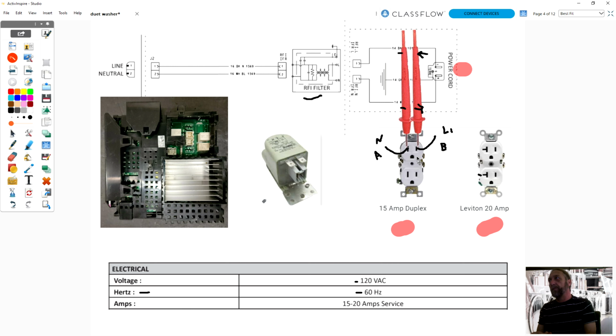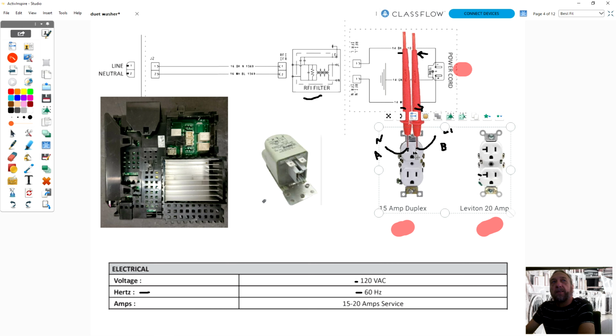Put one meter lead in the ground and one on the hot. So you leave one lead on the hot, and move the other lead to ground. If you have voltage, it's wired right. If you don't have voltage, go back and move your meter lead to the other hot. If you have voltage there instead, it's wired wrong. So whichever one gives you power to ground is the hot one, and that's how you tell if the left or right is hot, by using the ground.